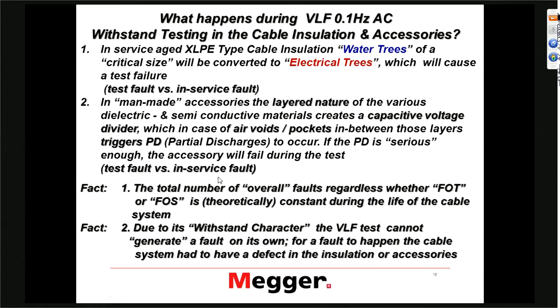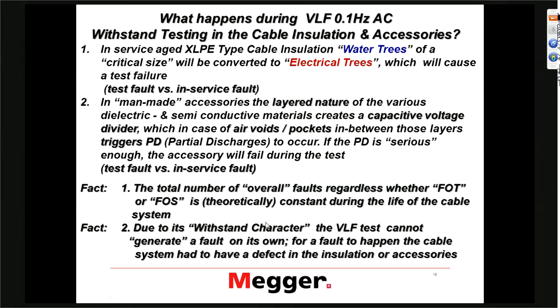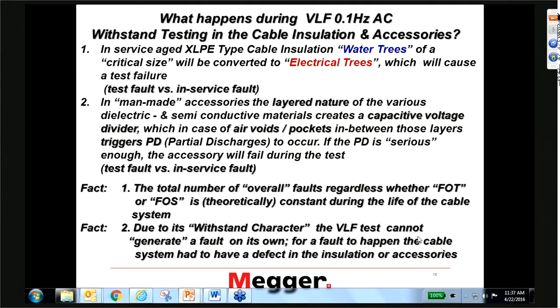Typically today, the thinking is: I'd rather have the cable fail under controlled conditions — that means during a planned outage — rather than in service when I have no control over it. Also, due to the withstand character of the VLF test, it cannot generate a fault on its own. If a cable fails during a withstand test, it only fails because the cable has a defect in the insulation or the accessory already. Otherwise, the test voltage cannot fail the cable. This has been proven over many years.